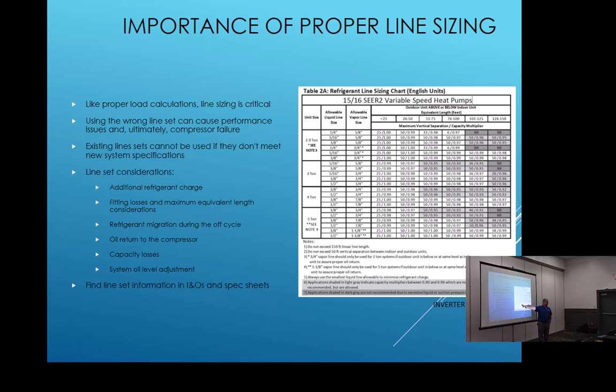Okay? The biggest part of that is they wanted to make sure that with the bigger suction line sets that you have, the velocity of that refrigerant flowing through that line is not as fast. So they want to make sure that they get the oil returned back to that compressor. That was their main objective of not wanting to use 1 1/8. But they've had some pushback over different jobs and different things like this, people complaining. So they are allowing a 1 1/8.